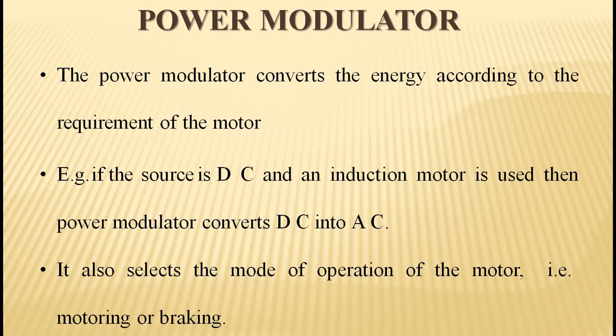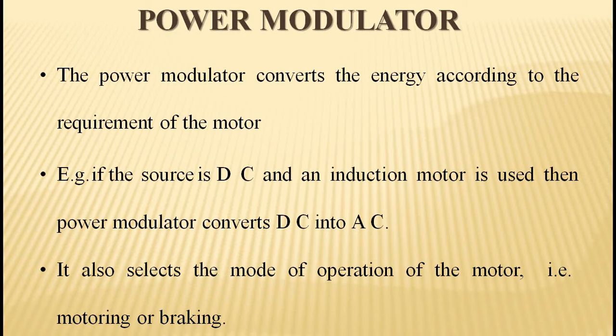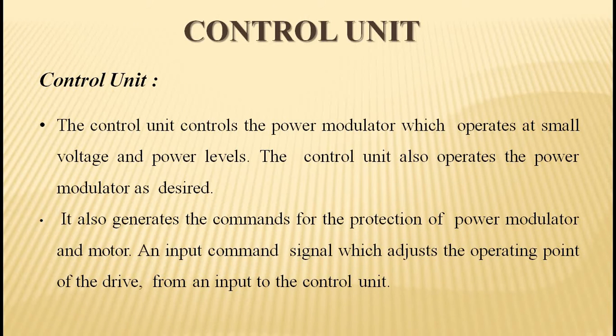The power modulator restricts the source and motor current to prevent overloading or voltage drop. It also converts energy according to the requirement of the motor — for example, if the source is DC and an induction motor is used, the power modulator converts DC into AC. It also selects the mode of operation of the motor, like motoring or braking.